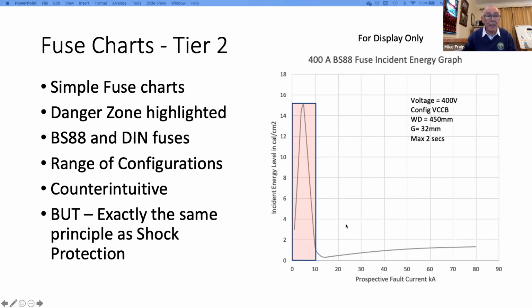I know it's counterintuitive because what we're saying is that fault level is your friend, from my early remarks, and at low volt it is. But it's exactly the same for shock protection. Your enemy in shock protection is impedance, which is exactly what reduces the arcing current, by the way. So, you need to have fault current in order to disconnect circuits within the required times for shock protection.